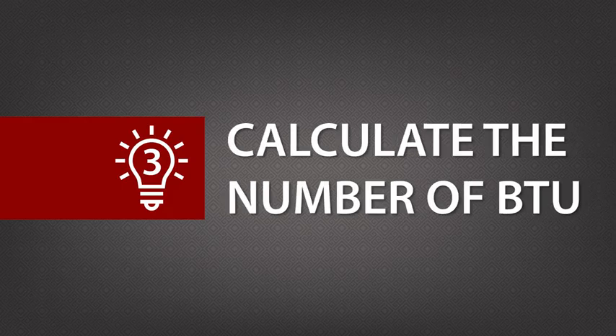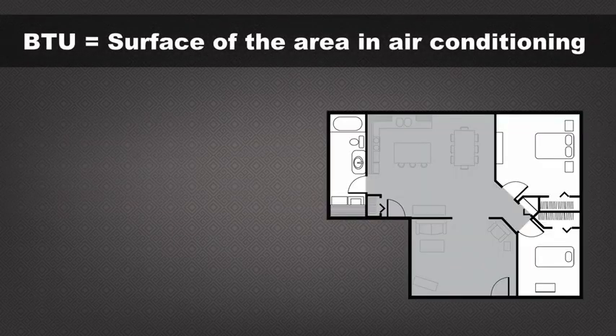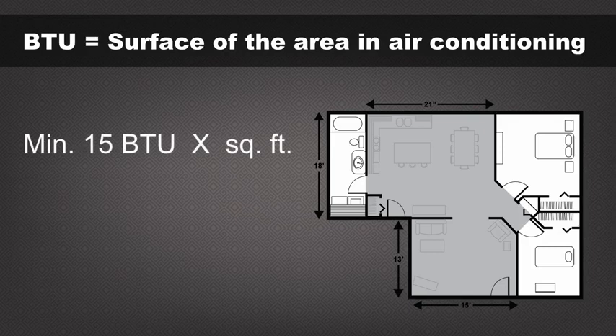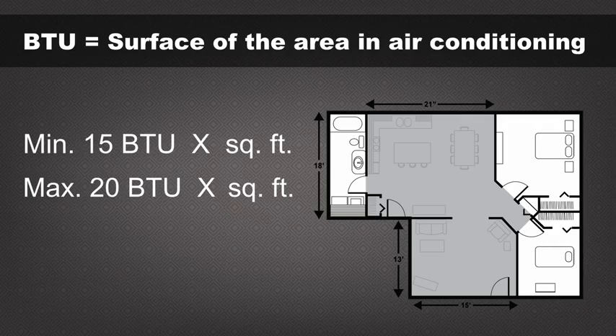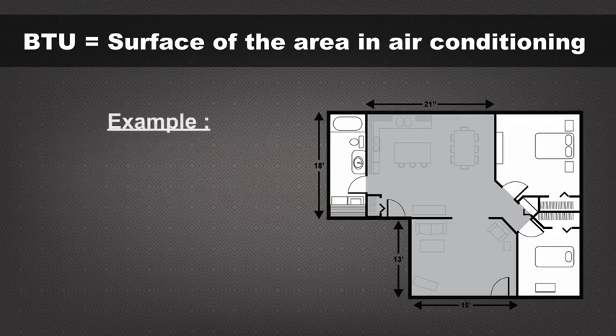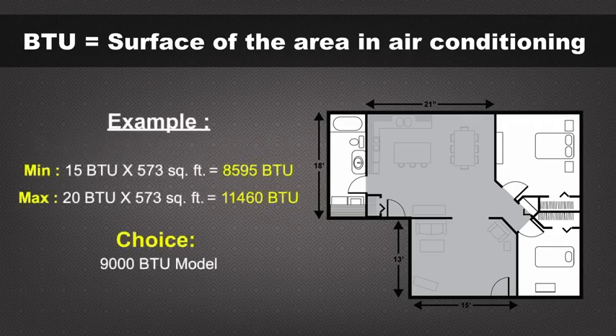Tip 3: Calculate the number of BTU. For a quick estimate, calculate a minimum of 15 air conditioning BTU and a maximum of 20 air conditioning BTU per square foot. Choose the heat pump model that has a BTU value between those two values.